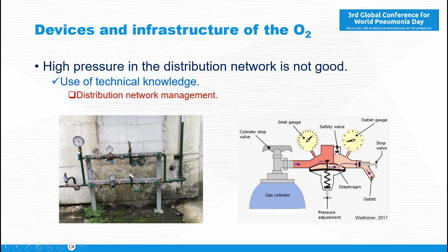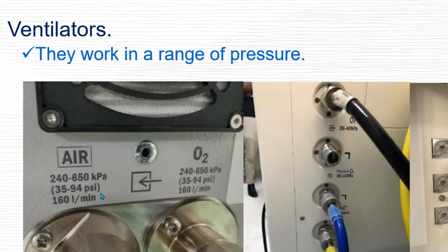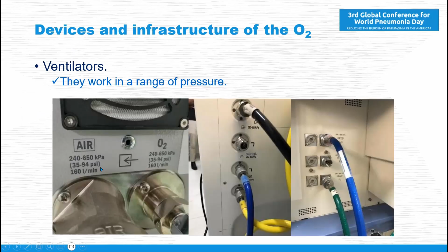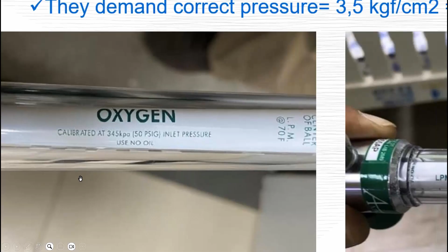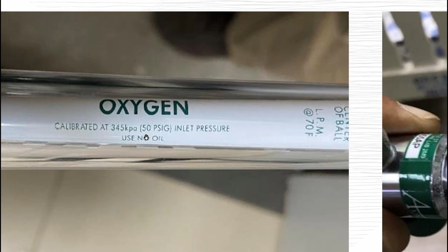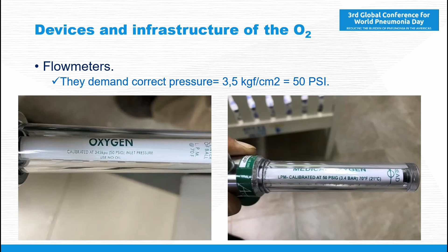Another very important point to be considered here is how we manage the oxygen pipeline pressure. Engineering must know how this simple equipment works in order to regulate the right pipeline pressure. Medical equipment such as mechanical ventilators or anesthesia machines normally works using a range of pressure, not a specific value. But in the case of flow meters, they are calibrated to work at a specific pressure. We can find in the Americas basically two values of pressure, either 50 psi or 60 psi.